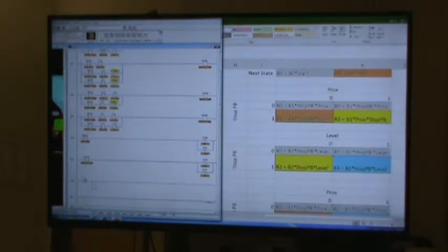When we're in the fill box state, what needs to happen? In fact, here, let me cheat a little bit. Let me save some time. I'm going to get rid of that last rung, copy and paste the rung below, and I'll just reference another bit. It's going to be the motor and the valve. In the fill box state, I want the motor off, and I want the valve on. See what I did there? Just unlatch the motor and latch the valve.